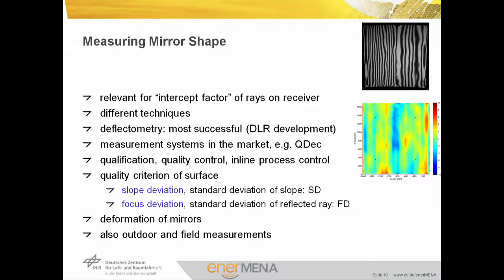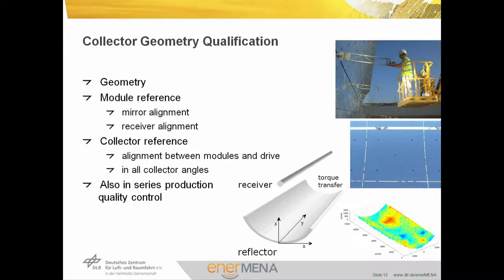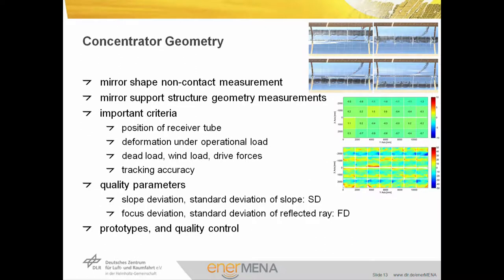These measurement techniques can be performed indoors and also outdoors in the field. Another way to measure is photogrammetry. Photogrammetry is used for 3D measurements of mirror shape and can be used to calculate optical efficiency or deformation effects. The picture shows the application of photogrammetry targets onto the mirrors and absorber supports to determine the geometry of a collector. We need a module reference to evaluate the mirror alignment and receiver alignment to each other. On the collector reference basis, we look at alignment between modules and drive at all collector angles, to determine any deviations from torsional loads due to friction or wind loads. This measurement is applied on prototypes but also in series production quality control. The concentrator geometry can also be measured with deflectometry when the collector is fully mounted.